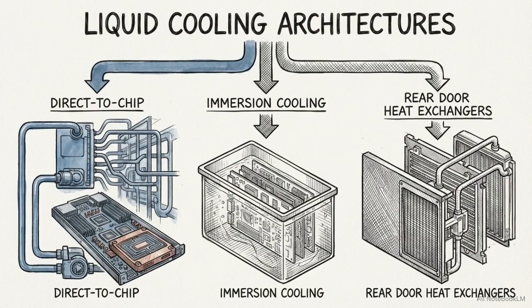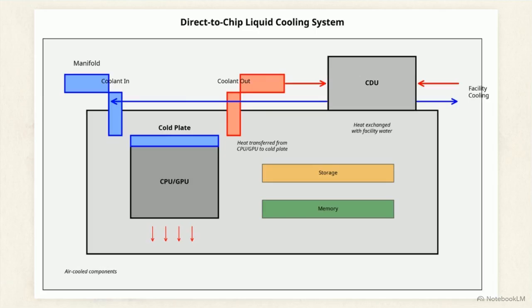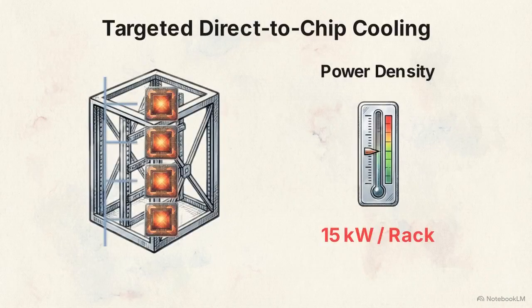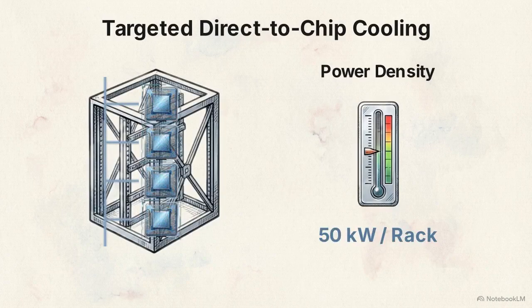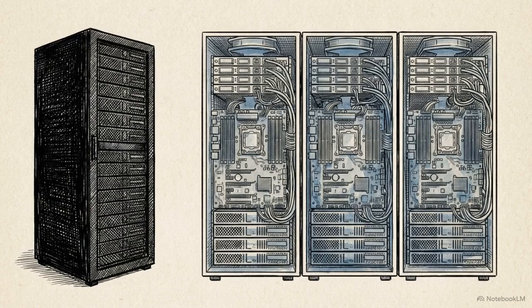The first is direct-to-chip liquid cooling. This schematic details a direct-to-chip system. The blue cold plate attaches directly to CPUs and GPUs. Liquid coolant cycles through, absorbing thermal energy. Following the red pathway, heated liquid transports into a coolant distribution unit, transferring heat to the main cooling loop. By targeting the heat specifically at its source, this approach supports 30 to 50 kilowatts per rack. That yields an immediate 2 to 3 times density increase over traditional air cooling.